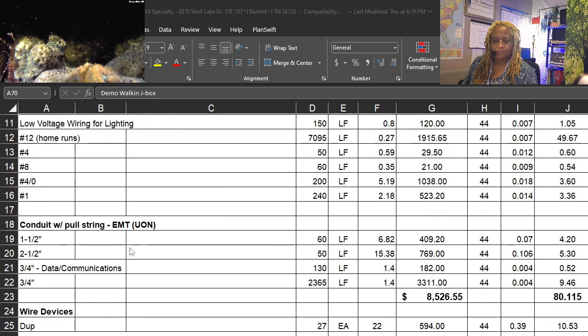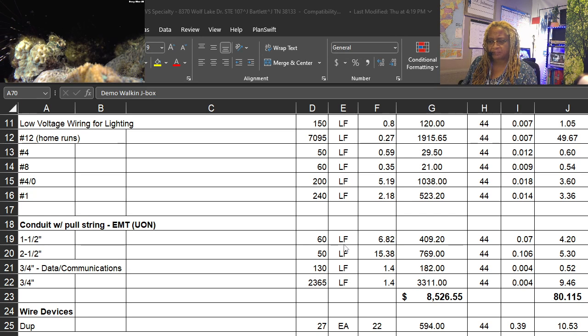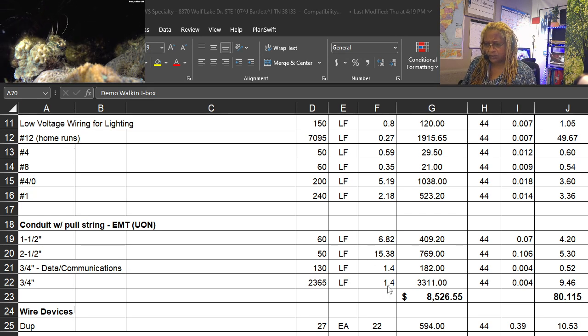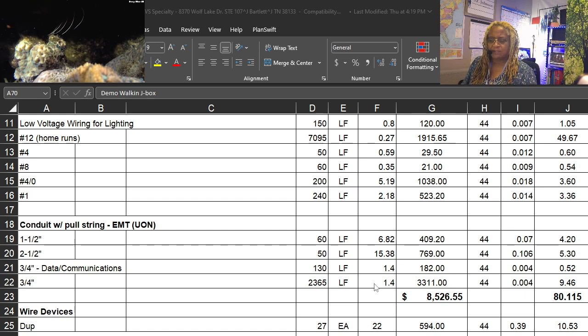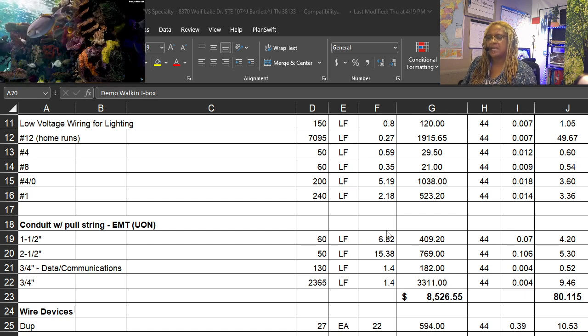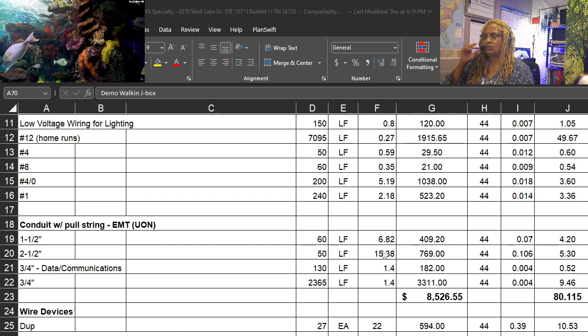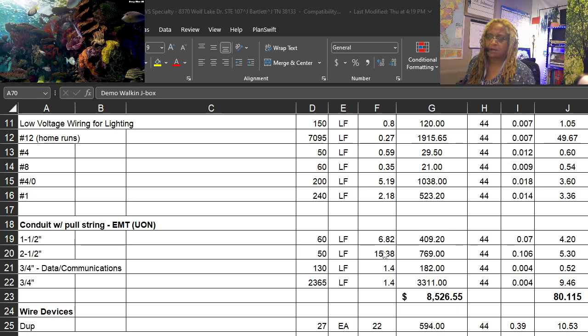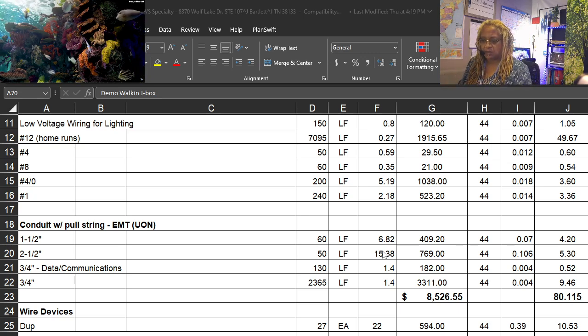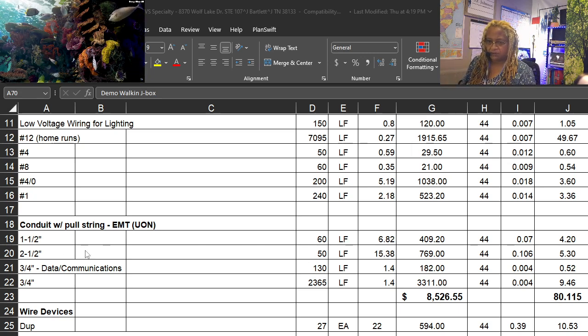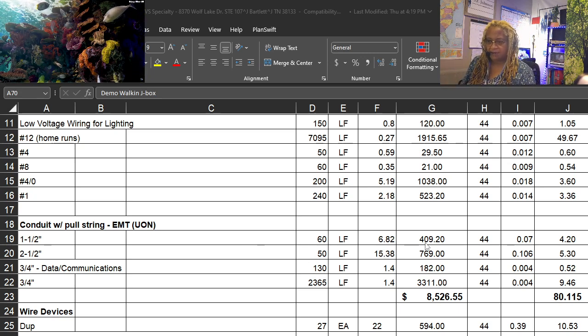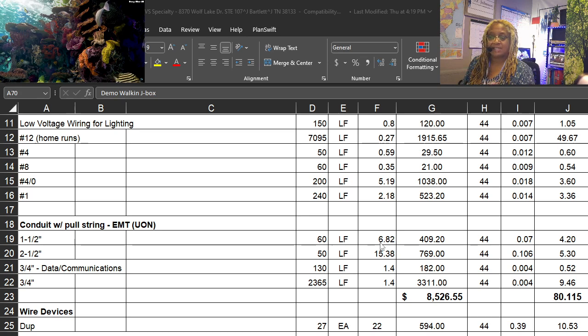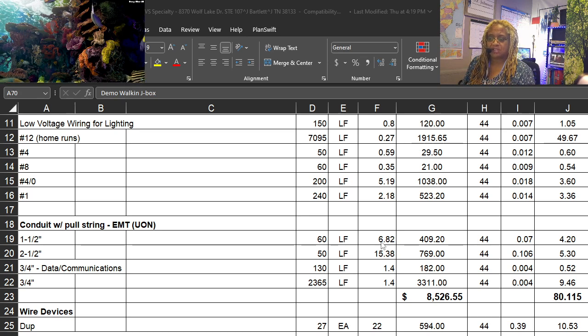For conduit, same thing. Now for conduit prices, rule of thumb, because you have to give the conduit and the pull string, is that it's twice the cost from your cost book. So one and a half, whatever the cost is, times two.